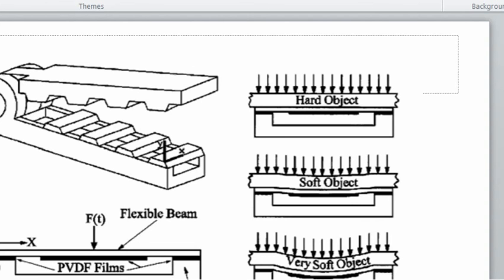At the Fraunhofer Institute for Biomedical Engineering in Germany, a vibrotactile sensor prototype was designed comprising an alternating current AC excitation coil, which generates an oscillating magnetic field to induce vibrations on a permanent magnet. The magnet, which is attached to an elastomer membrane located at the tip of the sensor head, can vibrate within a range of 100 to 800 Hz. The amplitude, phase and frequency of the vibrations are accurately measured using an eddy current sensing scheme. This involves additional components, including a conducting disc on the permanent magnet and a measurement coil located nearby.